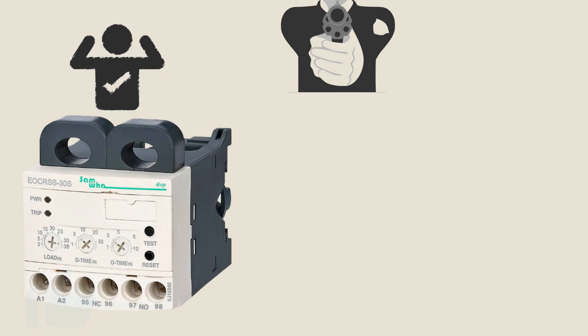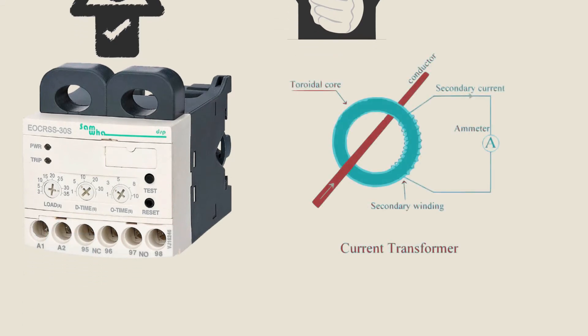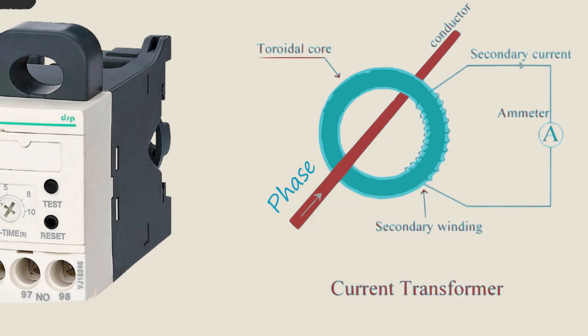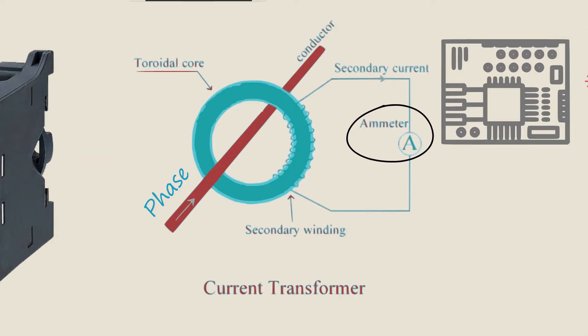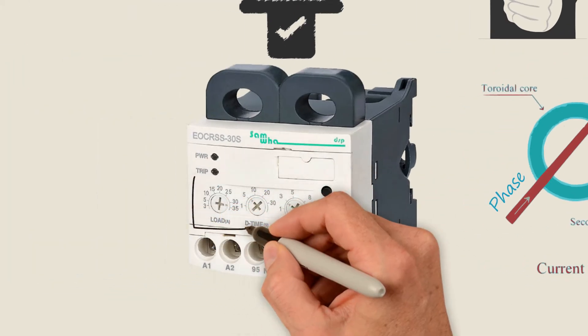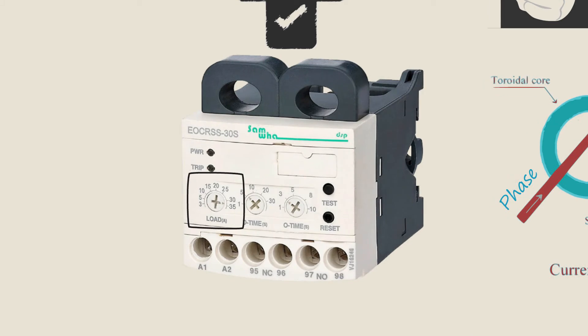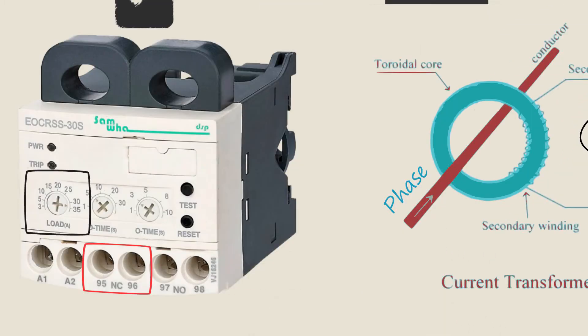All right, this is also an electronic overload relay that uses a current transformer mounted on each phase that directly measures current. Internal circuitry calculates the temperature based on a user-adjustable setting and will trigger the feedback contact of the overload to open in case of a continuous overload.